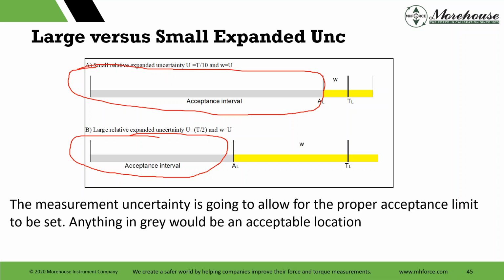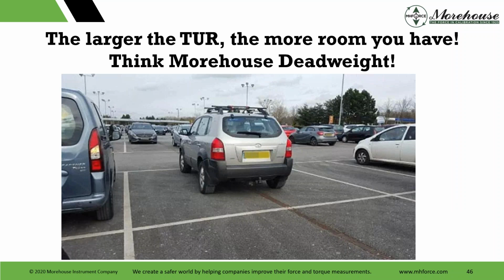If it fails, it's the whole investigation process. So the measurement uncertainty is going to allow for the proper acceptance limit to be set. Anything in gray would be an acceptable location in this one. I liken this to car spots, right? The larger the TUR, the more room you have. Think of dead weight machine primary standards.